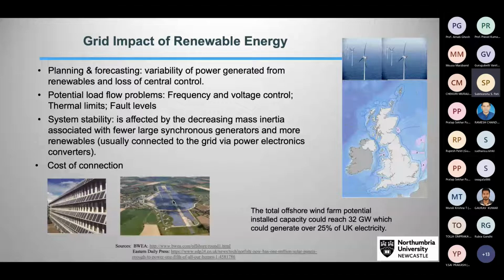So there is variability of power generated from renewable energy sources, and you lose central control, as we normally have. There is potential load flow problems with regard to frequency control, voltage control, thermal limits. Even fault levels may increase, although PV systems are connected through power electronics, so the contribution to fault level is not significant.